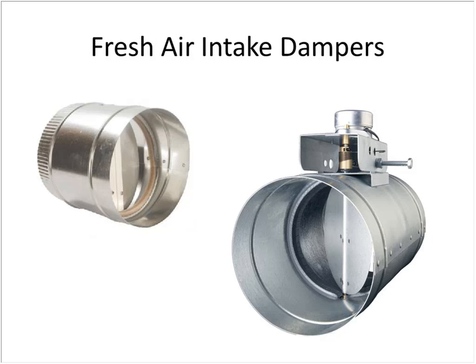The fresh air intake from ambient into the cold air return side, if you install those now, they have to have intake air dampers on them, so that when the air handler is operating, the damper opens up electrically, and it closes when the air handler is off. The gravity dampers, if they're allowed, typically result in too much air leakage through them when you're doing the duct leakage testing. They can account for 30% of your leakage to the outdoors if they don't seal. So mechanically operated dampers are the best option for air intake on a furnace. Now, if you have an ERV or HRV, a heat recovery ventilator or an energy recovery ventilator, then these dampers aren't required at all.